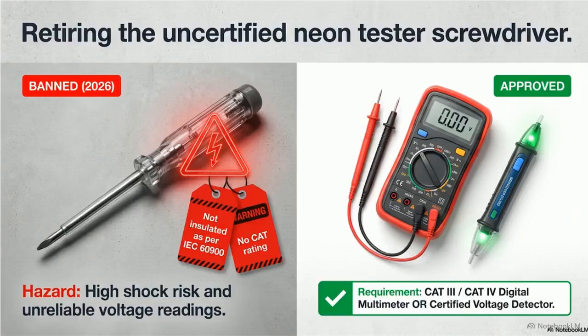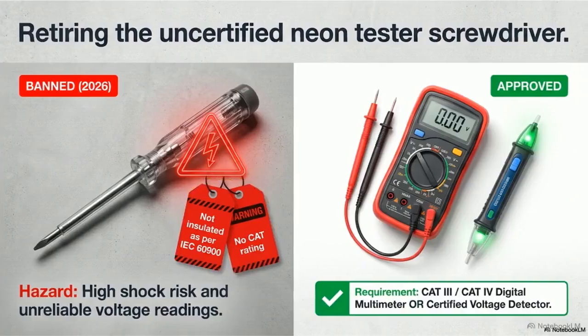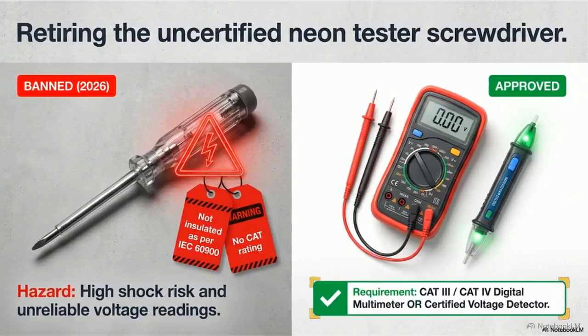This graphic eliminates the uncertified neon tester screwdriver on the left. It lacks insulation, posing high shock risks and giving unreliable readings. On the right are mandated replacements. You must now use a Category 3 or 4 digital multimeter or a certified voltage detector.